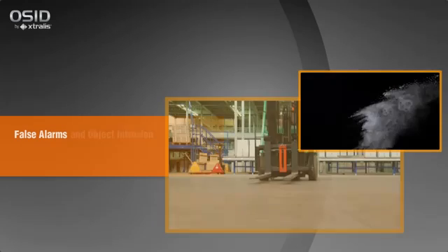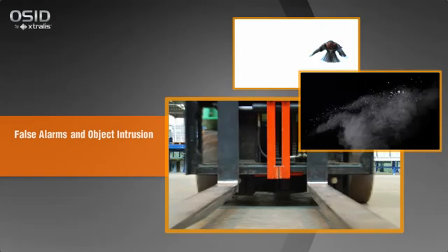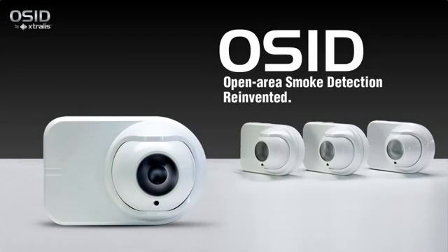While common, traditional beam detectors are susceptible to building movement and prone to false alarms due to dust and object intrusion. They are also difficult to align and therefore time-consuming to install. Xtralis has reinvented open area smoke detection with its latest patented innovation, Open Area Smoke Imaging Detection or OSID, which overcomes the weaknesses of traditional beam detection to provide reliable, cost-effective protection for open spaces requiring only standard sensitivity detection.